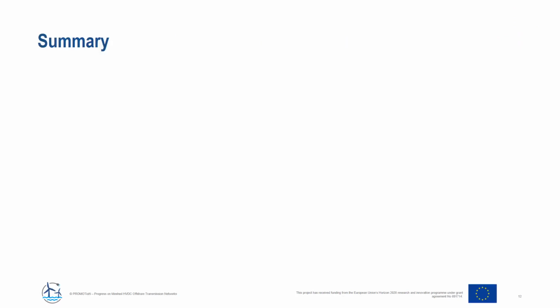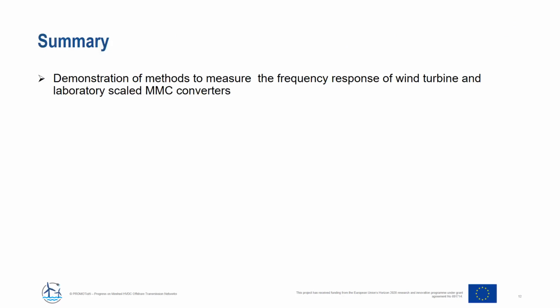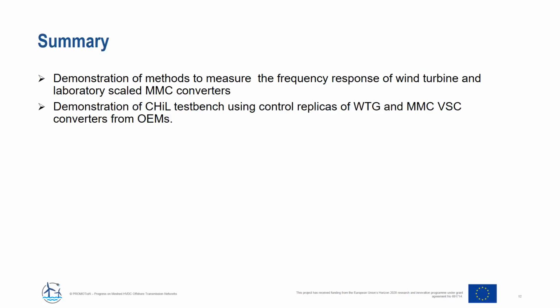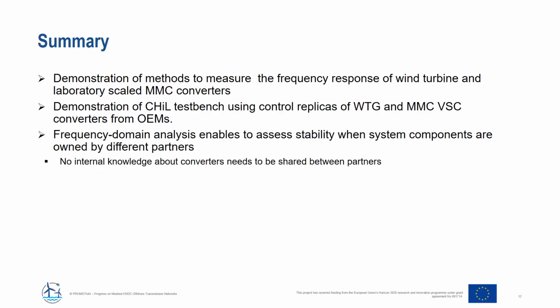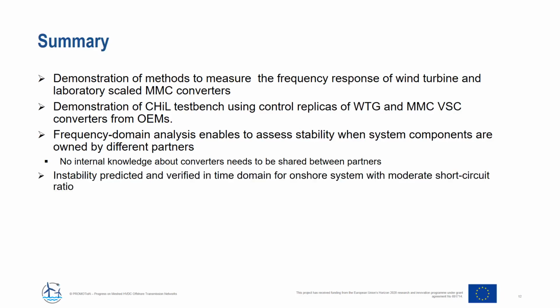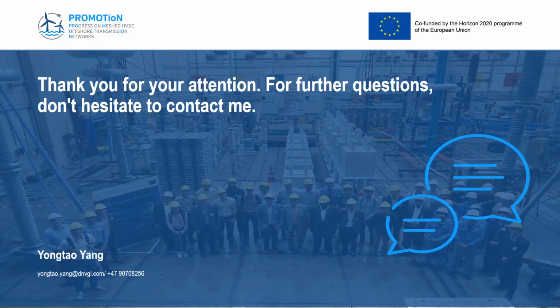To recap this session, we have demonstrated the method to measure the frequency response of wind turbine generators and laboratory scale MMC converters. We also demonstrated the control hardware in the loop test bench using controller replicas of wind turbine generators and MMC VSC converters from vendors. The frequency domain analysis enables us to effectively assess harmonic stability. Even if you have system components owned by different partners, no internal knowledge about the converter needs to be shared among the partners. We predicted the instability and verified it in the time domain simulation for the onshore system with a moderate short circuit ratio. Thank you.